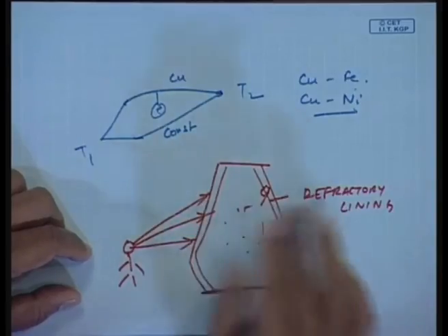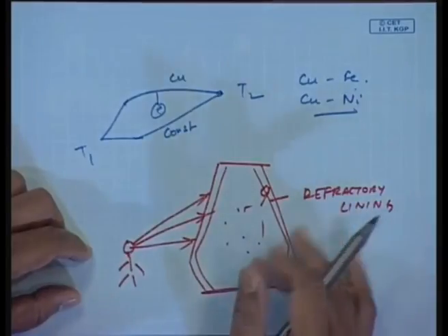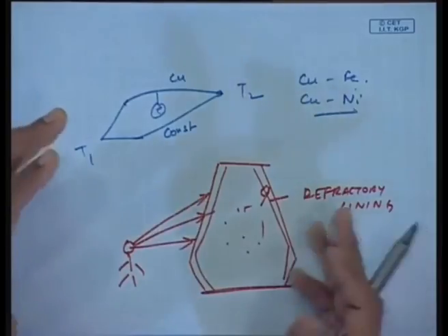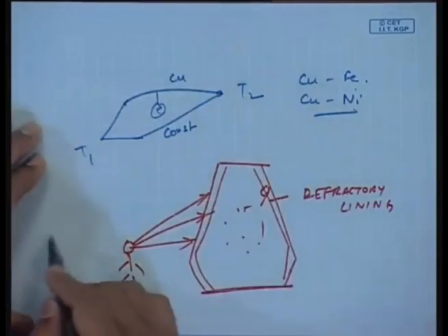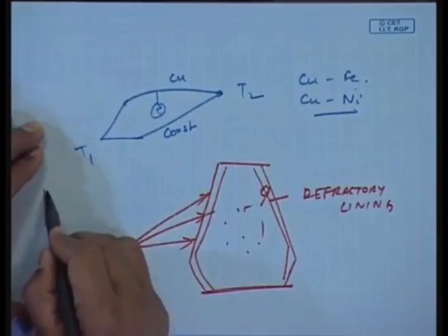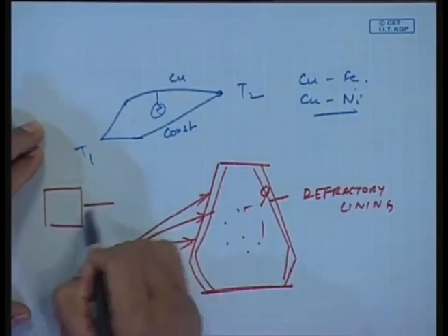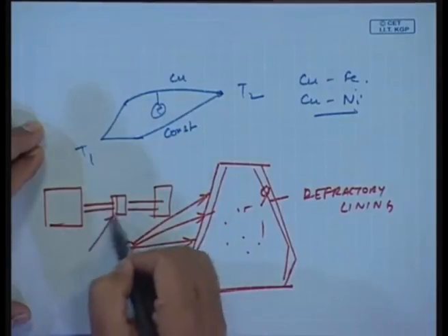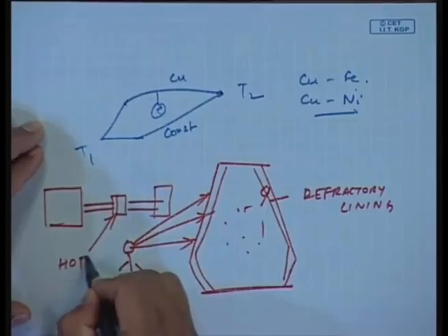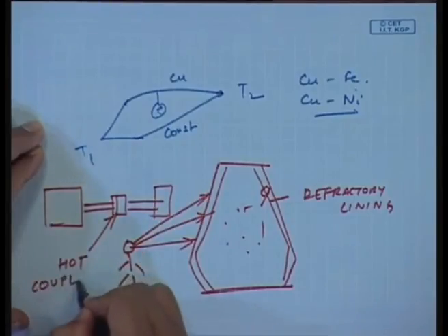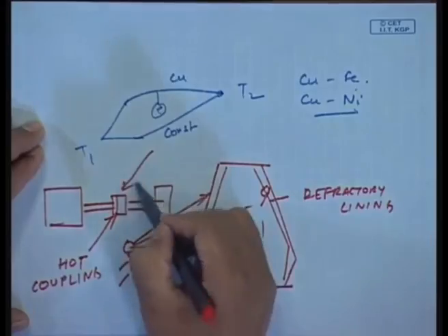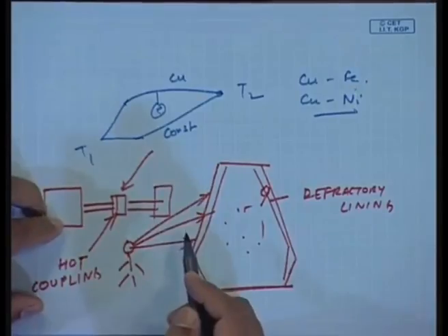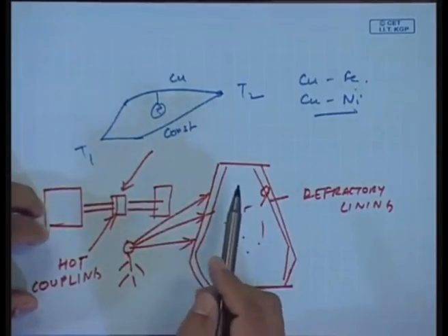So, CBM does not always mean dynamic signals, but these give us some clue as to what could possibly be wrong with the system. For example, another place is a pump, or a motor driving a pump, where because of misalignment the coupling is becoming hot. From a far off place I could use a temperature detector and see the temperature of the coupling, the temperature of the bearing, etc. So, I can do that.